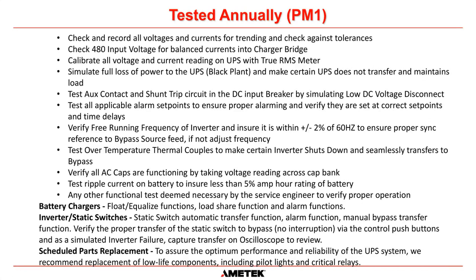We also verify the free running frequency of the inverter because the inverter has an internal quartz oscillator on the control board in all of our UPSs. Basically, if we lose our bypass supply and we have no reference frequency or voltage to synchronize to, then the inverter will default to its 60 hertz crystal in North America, and it will run at exactly 60 hertz. And we have to test that to make sure that that circuit is functioning. And all we do is remove the bypass supply from the UPS and then test what the frequency of the inverter is.